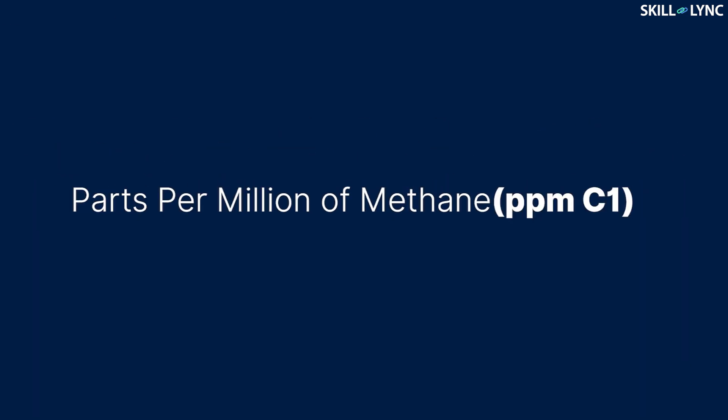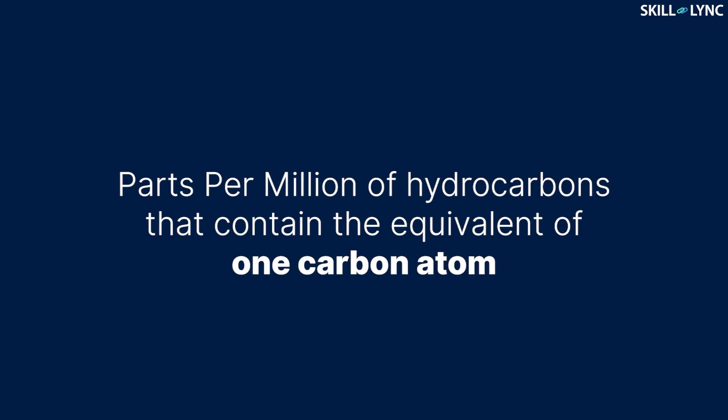That is, the response produced in the detector for butane, a four-carbon compound, will be four times that of methane, a single-carbon compound. Hence, the flame ionization detector acts as a carbon counter. Hydrocarbons are measured and expressed in the units of parts per million of methane — that is, parts per million of hydrocarbons that contain the equivalent of one carbon atom.